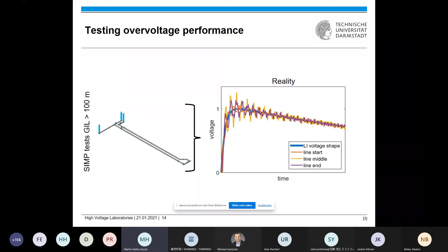And this can result in higher voltages at positions on the HVDC GIS. So this means that you make the test more critical than it should be. So maybe you provoke a flashover, but this is not because the system is not well designed, it's because the testing is not well designed. So this means that you have to do something to improve the testing.